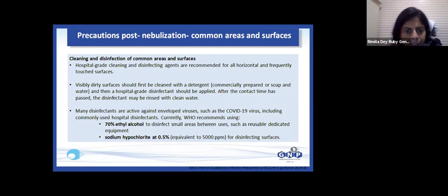Specifically for the care of nebulizers, the nebulizer should be cleaned daily in regular usage and after each use in intermittent use. The mask, mouthpiece, and the chamber should be disconnected, disassembled, and washed in a warm detergent and water solution. I do not know whether it is practical for every use in the patient, but if it can be done at least once in a day, that is a practical target that can actually be helpful for your patients. And the components should be left to dry overnight.